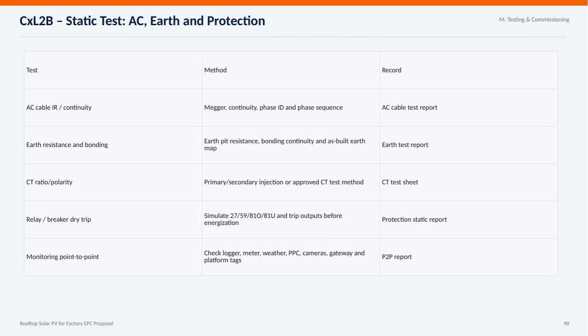Here we have the CXL2B static tests focusing on AC, earth, and protection systems, which are crucial parts of the rooftop solar PV installation for the factory EPC proposal. First, for the AC cables, we perform insulation resistance and continuity tests using a megger tool, along with phase identification and sequence verification, all documented in the AC cable test report. Next, earth resistance and bonding are tested by measuring the earth pit resistance and verifying bonding continuity, supported by an as-built earth map, with results compiled in the earth test report.